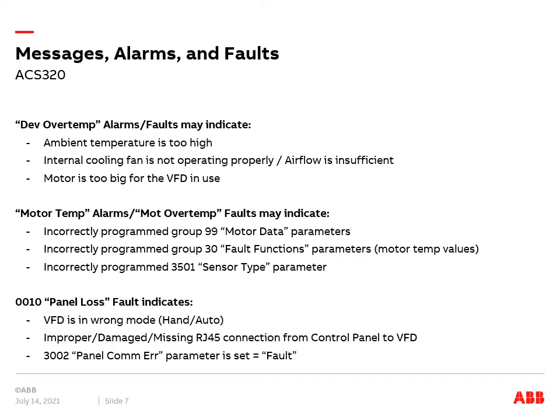The various motor temperature alarms and faults usually indicate the VFD parameters are not programmed correctly. Check groups 99 and 30 and also parameter 3501. Panel loss is the VFD saying the connection between the VFD and control panel has been severed when in hand control. Check the integrity of this connection. It can also be triggered when parameter 3002 panel comm error is set equal to fault, and it should not be.